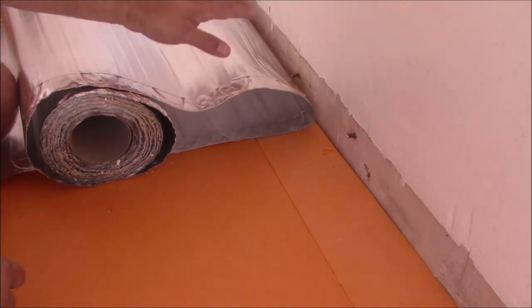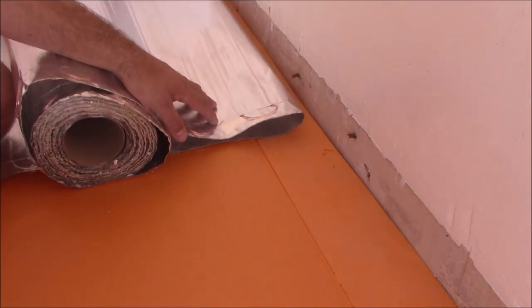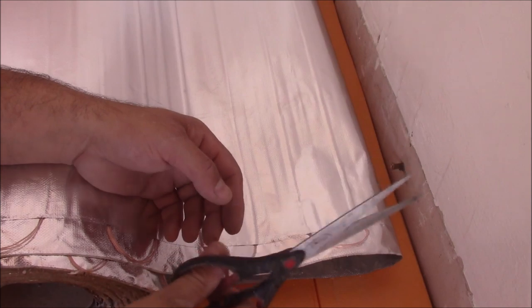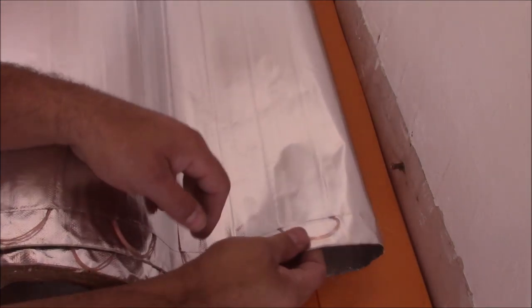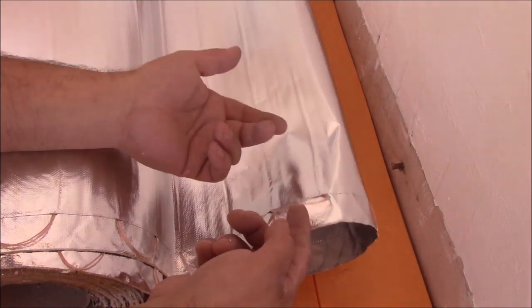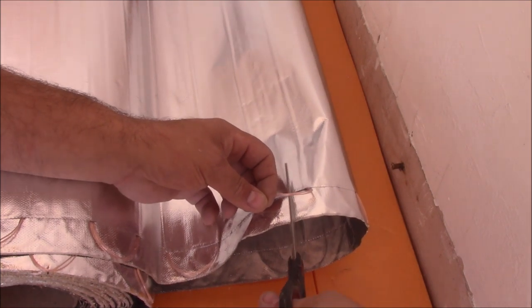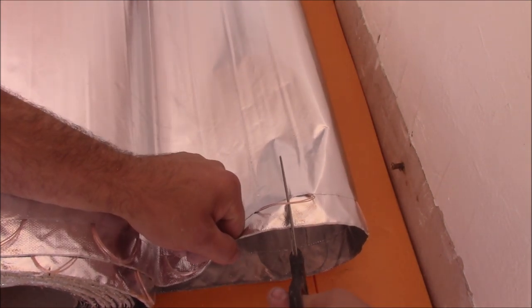So now when you come to the end of the wall, obviously you need to cut this mat. You need to use scissors to do it. You can cut the foil, but don't cut these wires. When you cut the wires, the mat is damaged and it's not going to heat. So basically what you do, you just cut under the wires.